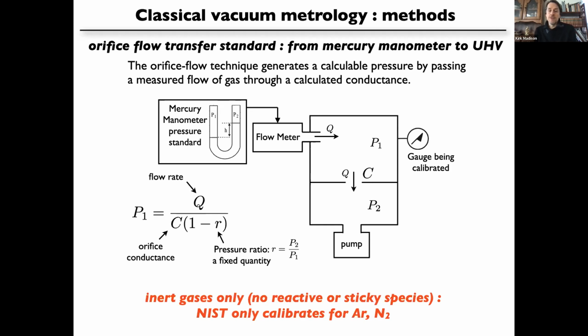So basically, NIST uses this. In fact, all metrology groups worldwide use this method to calibrate ionization gauges. And you can see on the right, there's a gauge being calibrated. It's connected to this pressure cell, and you create a known pressure P1, and you measure the gauge response, and that allows you to calibrate the gauge.